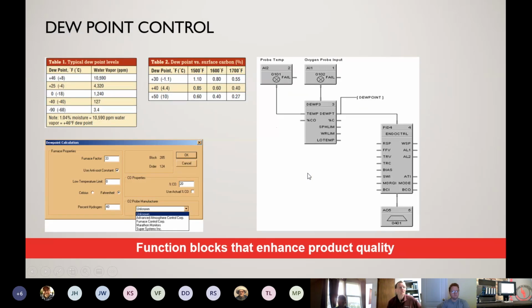Dew point control is another application where, using several function blocks, you can do carbon or dew point control. So you have a temperature probe, an oxygen probe input, going to a dew point calculation block, and then in return feeding a PID function block with an analog output.